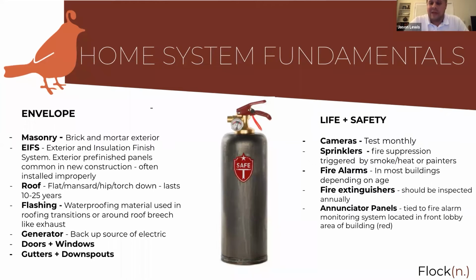I remember I got a call regarding a sprinkler head that had busted, and went to the property. When I went into the basement area where the dry system was, unfortunately the sprinkler head that we needed to access was in someone's storage unit. They lived overseas in Europe. So myself in my suit went and shut down the fire system because no one was going to come out for multiple days. And that could have been avoided if we had a proper maintenance plan where there was draining out of the dry system to make sure that all that residual water that was being captured inside of that was being moved through the system.